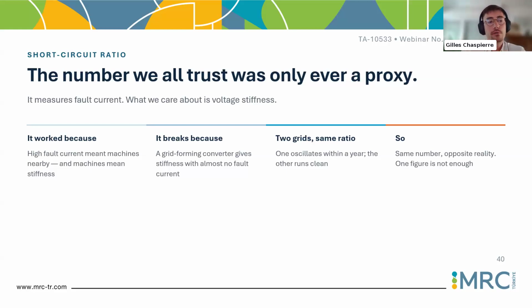So at early stage of a project, you need to have a simple indicator that can tell you how strong is my system. And the most famous one, simply because it's very easy to compute, is the short circuit ratio. The problem with the short circuit ratio is that it has been used for years and years by transmission system operators, and it's quite accurate, but as long as your system is dominated by classic synchronous generators. So with classic thermal units or nuclear power plants, hydropower plants, but with rotating masses, I would say, that can provide high fault current.